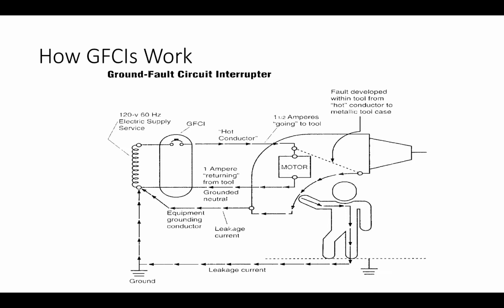So again, the GFCI breaker takes a look at the hot conductor and measures the amperage. Then it looks at the return amperage from the grounded neutral. If you lose any difference, it means that there's current leaking someplace to ground. The whole object is that the breaker will trip.